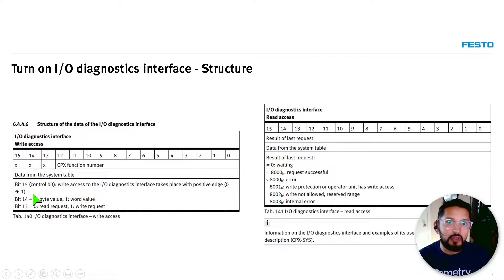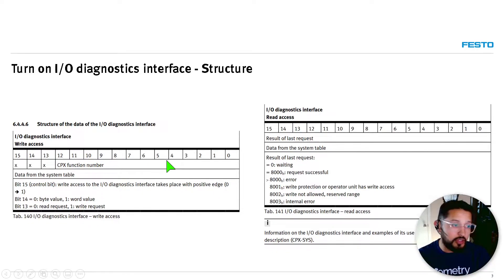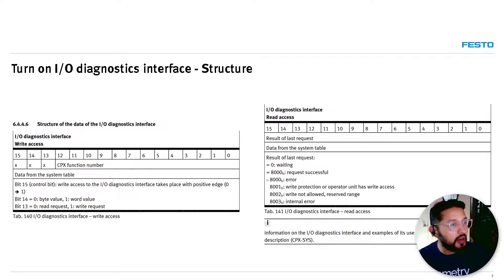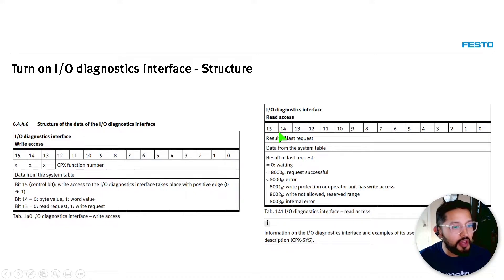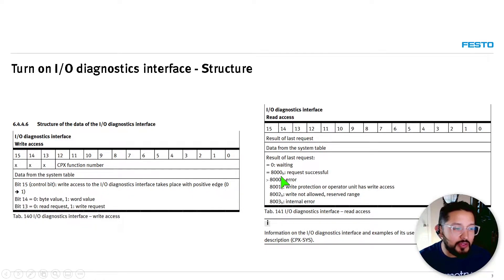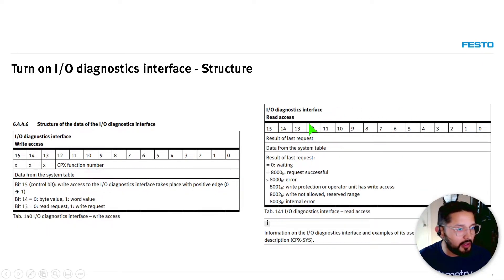Bit 15 is the execute bit — it triggers the request. Once you write this on the outputs, you get a response on the inputs, described in the read access table. If you get 0x8000 in the first word, that means the request was successful, and the actual result data comes back in the second word.